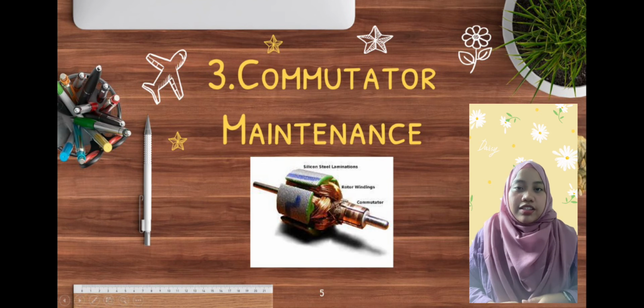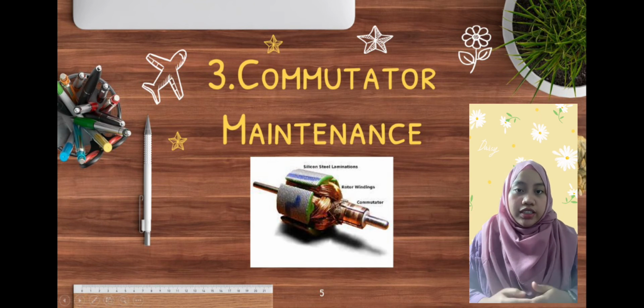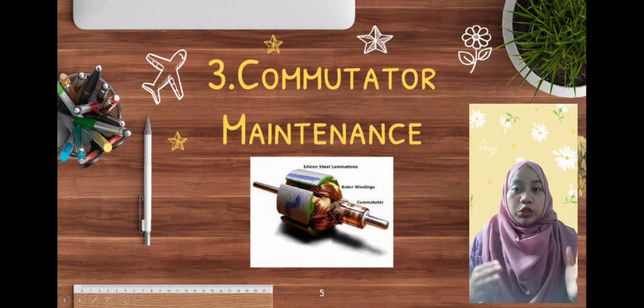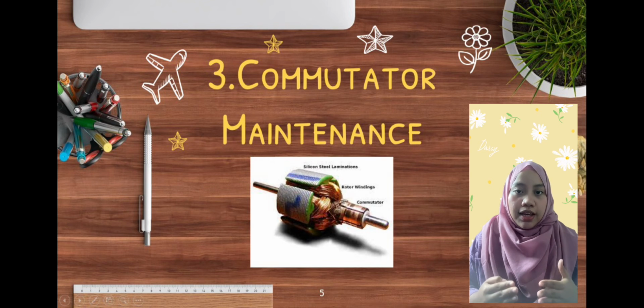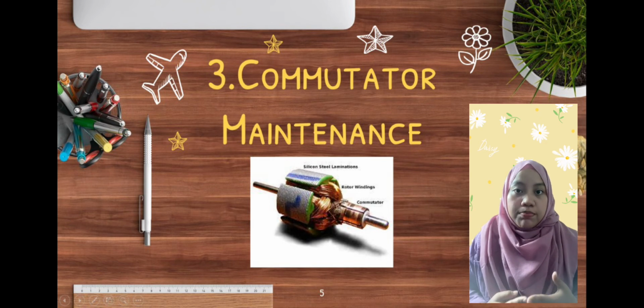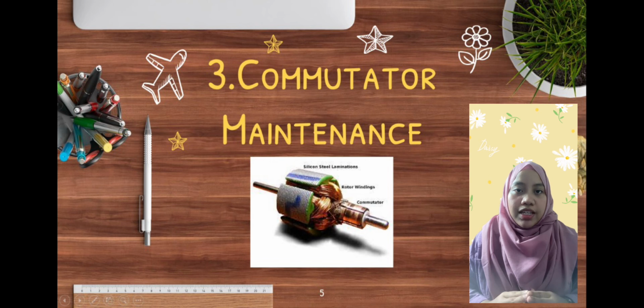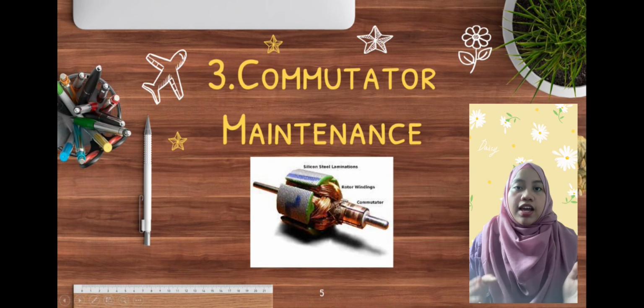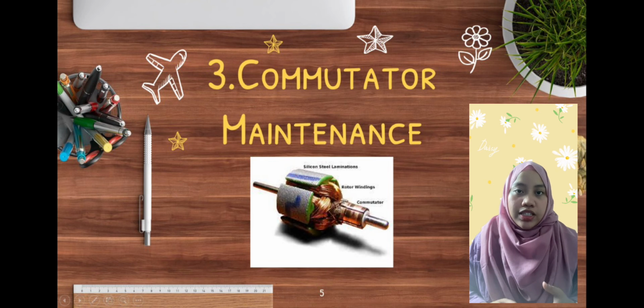Okay, the last one is commutator maintenance. Like carbon brushes, the commutator requires maintenance from time to time. The bars on a commutator must be maintained by way of machining the segmented commutator bars through. The segments are insulated between bars with a molding mica. Some larger DC motors may be able to be machined on site to prevent unnecessary extraction of the motor.